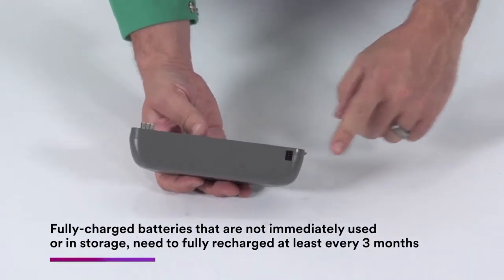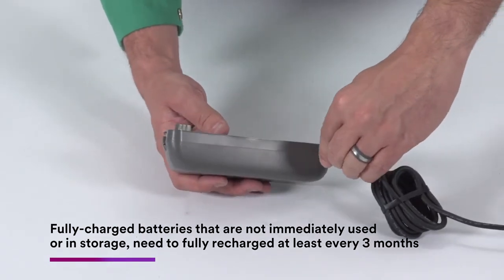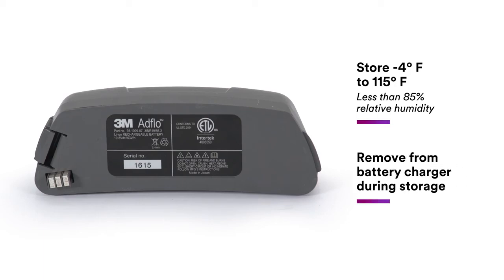Battery packs not intended for immediate or regular use should be charged upon receipt and then recharged every three months. They should be stored from minus four to 115 degrees Fahrenheit, at less than 85% relative humidity. The battery pack should not remain on the charger for more than three to four days to maximize battery life.